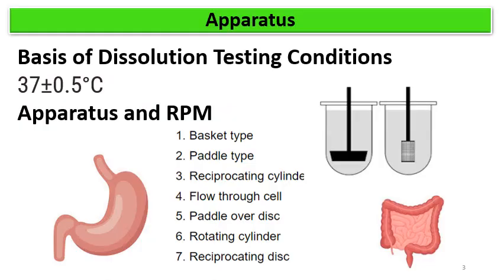There are various apparatus for dissolution testing. As per USP, there are 7 apparatus, and generally the temperature of the media is kept at 37°C with a variation of ±0.5°C. Up to USP-4 dissolution apparatus are used mainly for oral solid formulations. Basket and paddle types are USP-1 and USP-2. Reciprocating cylinder is USP-3, and flow-through cell is USP-4.